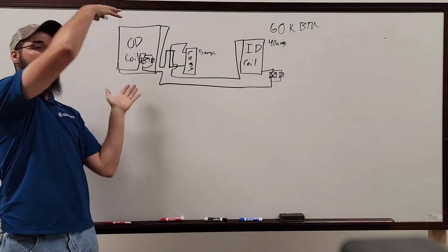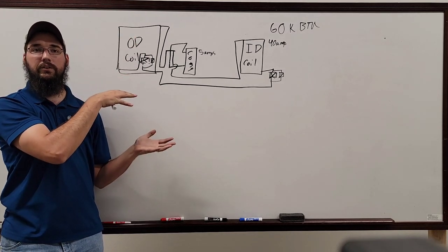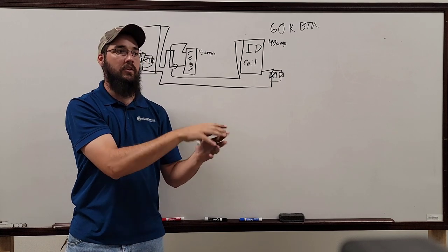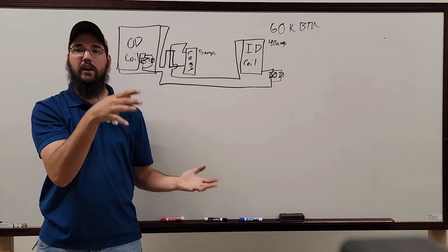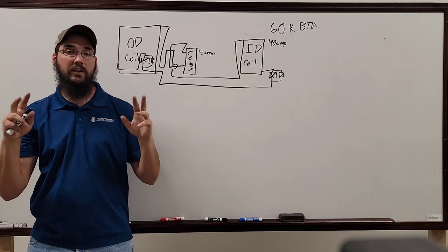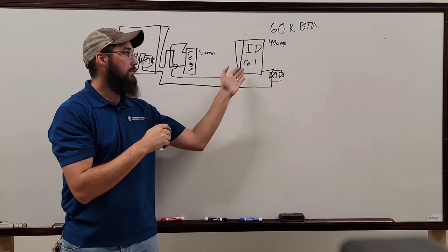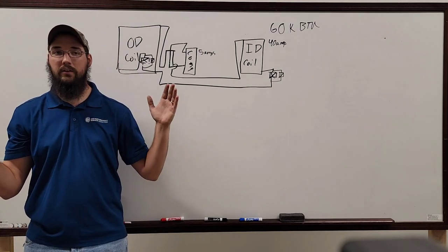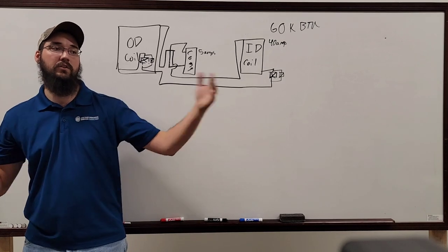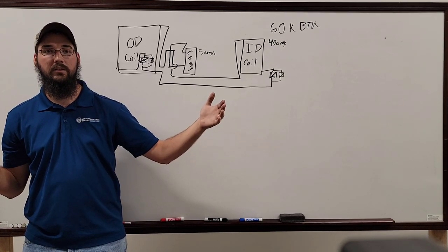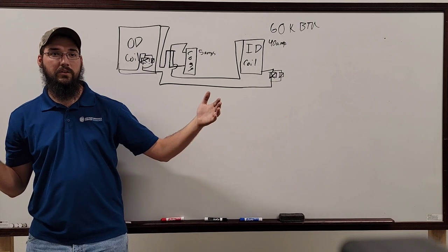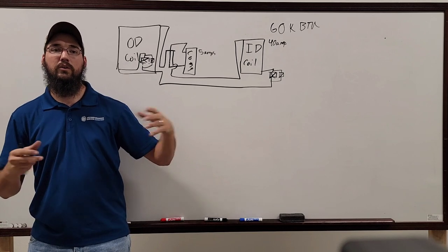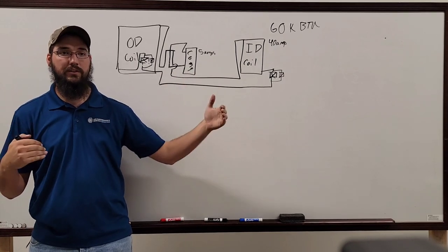Because you've got to think, look how big a typical outdoor coil is, and look how small a typical indoor coil is. Just in the sake of surface area, they may move the same capacity, but we have to achieve a much higher differential between air temp and coil temp to exchange the same amount of heat, right? So to accomplish the same heat exchange, BTUs, we have to have a higher delta.